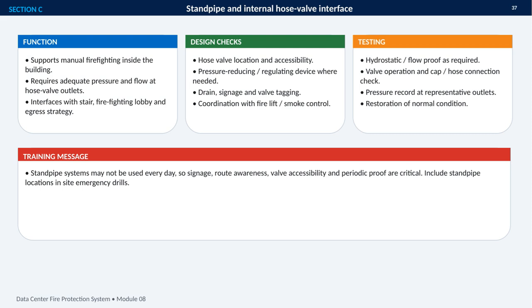That includes hydrostatic or flow-proof where required, checking valve operation and caps or hose connections, recording pressure at representative outlets, and restoring the system to its normal condition afterward. The broader training message is equally important. Periodic proof and route awareness are critical. Because standpipes may not be used every day, their locations should be included in site emergency drills, along with practice finding and operating the valves.